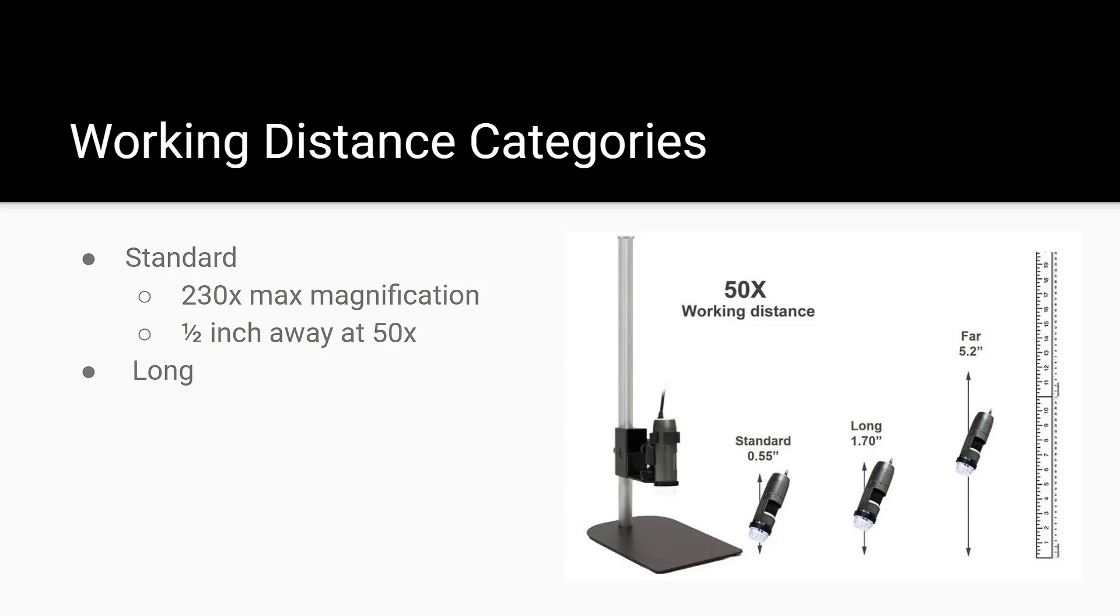Long working distance models have a magnification range of 1 to 140 times, and at 50 times magnification, you will have a working distance of approximately 2 inches.